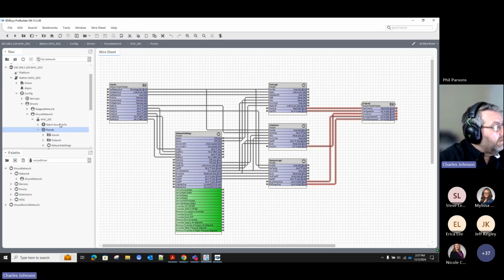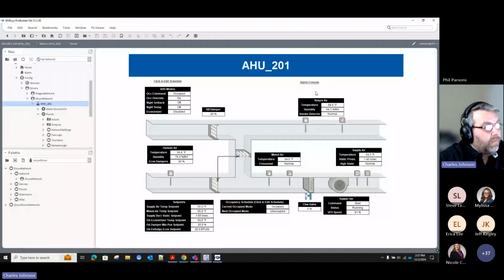Now, once you have all that, you can actually build a graphic the same way you would build any other Niagara graphic — using KitPX for SVG, your KitPX graphics, your KitPX HVAC, or if you had additional custom images, you can certainly do that too. As you can see, I do have some values that are reading for demo purposes, so we can see the fan running, chill water valve trying to maintain, and our dampers open 20%.